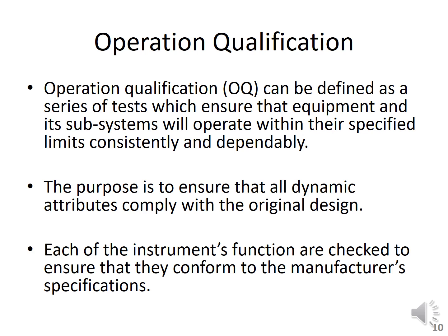Operational qualification should be approved before the protocol is executed, right? Whichever protocol you are going to follow, before executing it you have to approve the operational qualification. Each of the system's functions is checked in the operational qualification to ensure that they conform to the manufacturer's specification. If we say it in easy words, we operate it and see it, after installing, we properly operate that system, that machine, before starting it in the system.